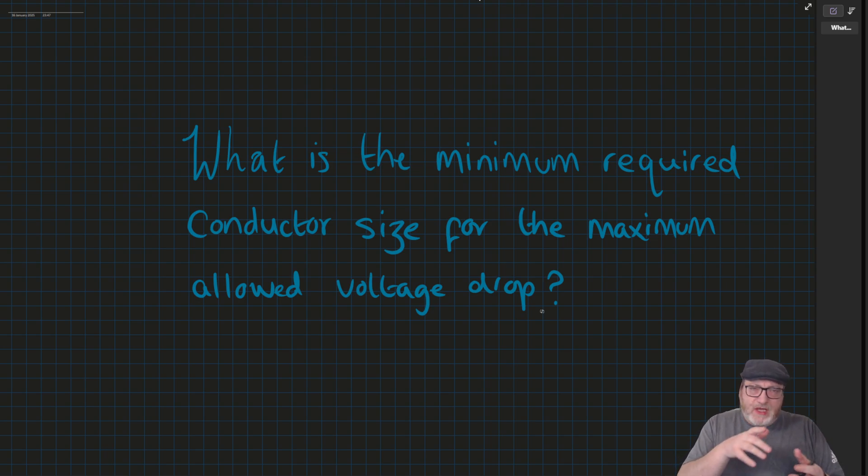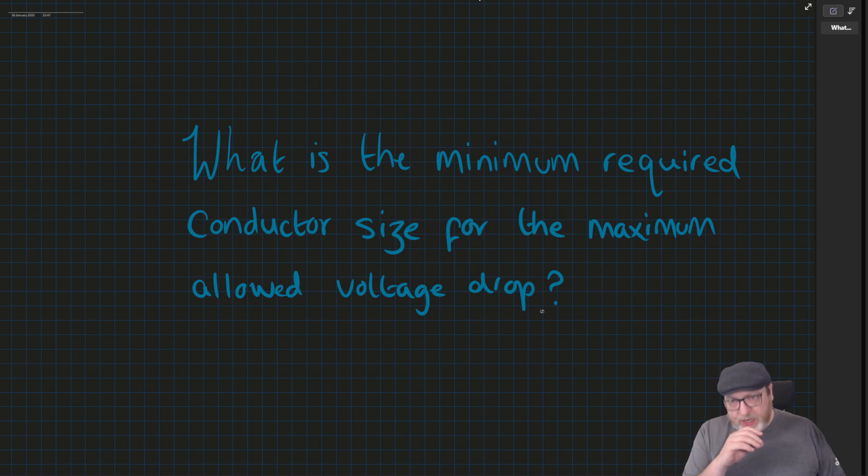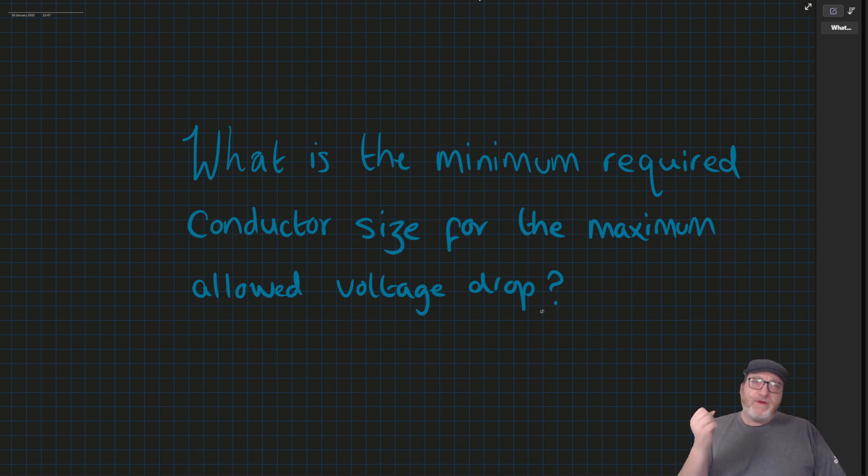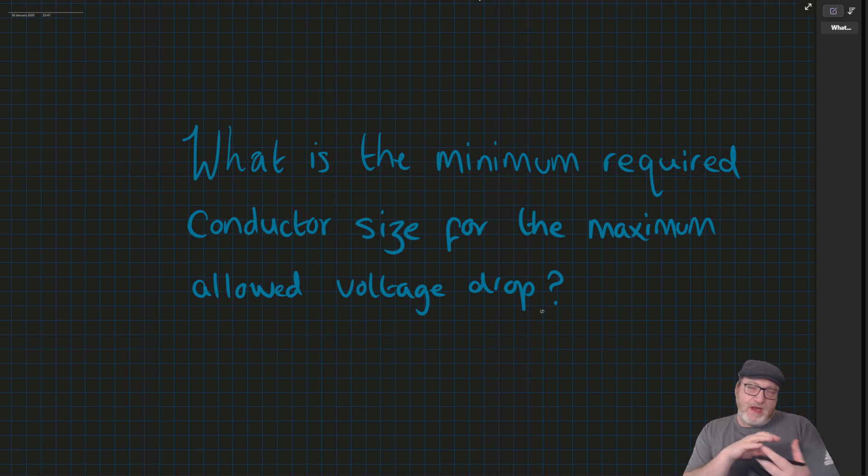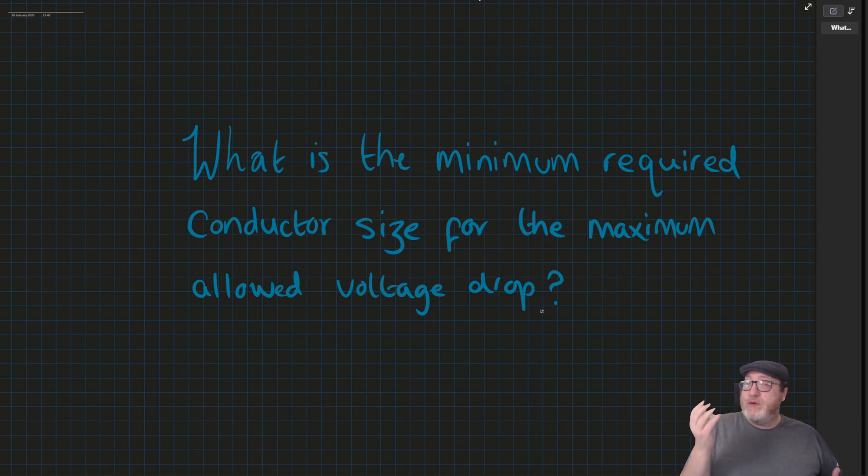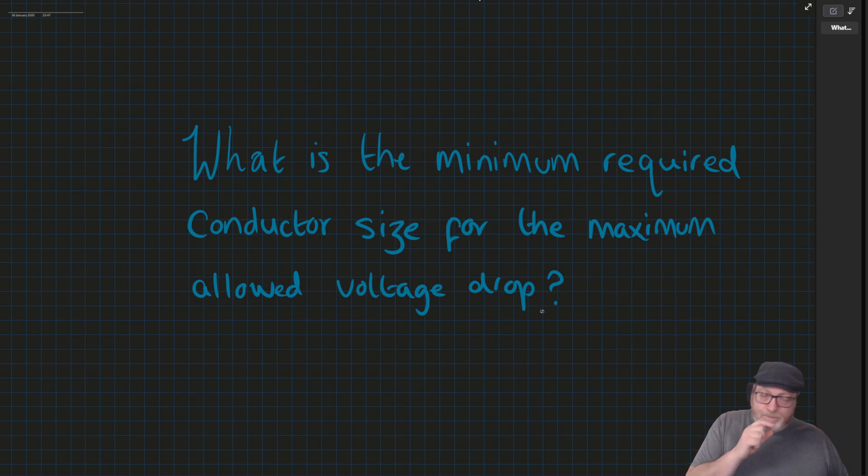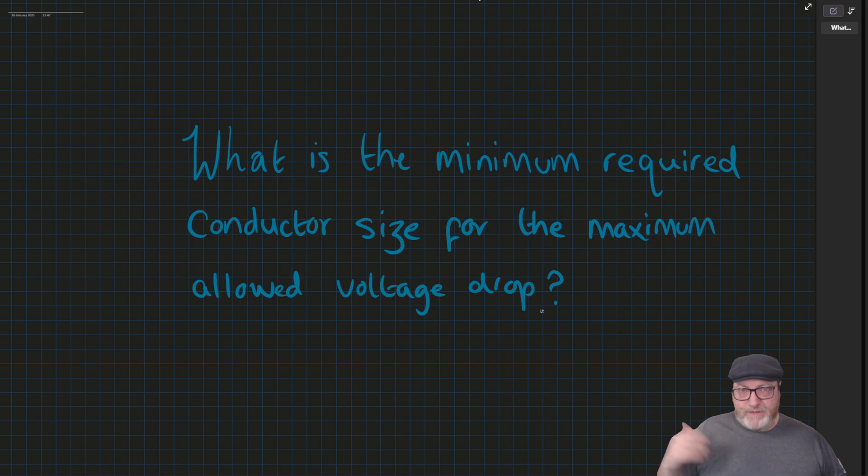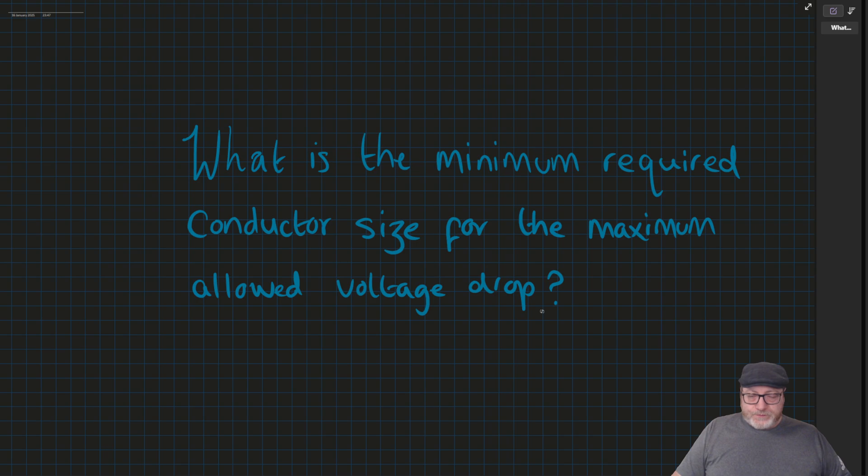So you've worked out the IB, the IN, the IZ. And then instead of just working the volt drop out straight away with what you've done, it asks you a question of volt drop, but kind of like a start fresh question, where it asks you what would the minimum required conductor size be if you were just to think of volt drop alone and not everything else you've just done. It can catch a lot of people out. So what I want to do is just cover an example.